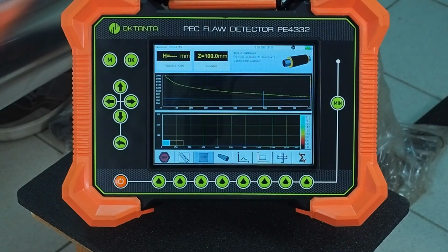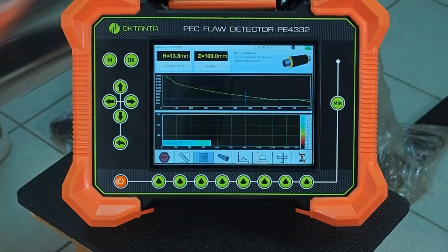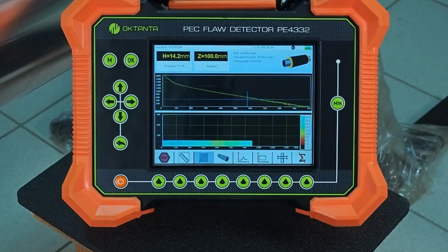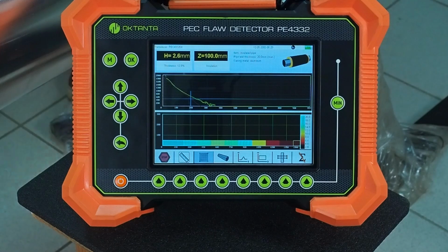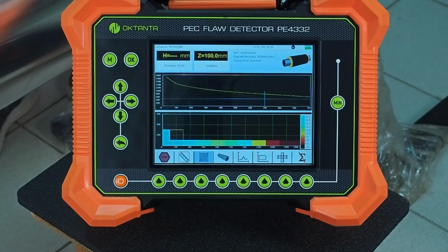With both options, we'll get the same color scheme of the pipe section, and the boundaries of the thickness difference are clearly visible on the plotted C-scans. The red zone with a wall thickness of less than 5 mm is most remarkable.